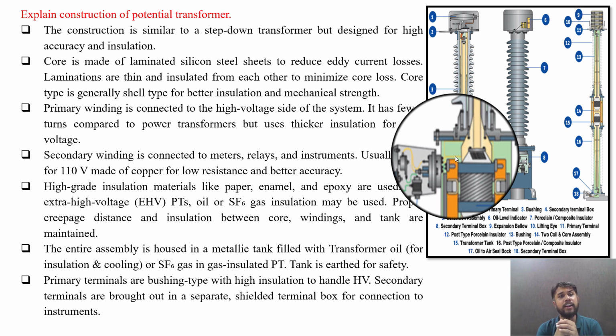This primary winding is connected to the high voltage side of the system, and it has fewer turns compared to the power transformer but uses thicker insulation for high voltage system. Secondary winding is connected to the meters, relays and instruments, usually rated for 110 volts, and the windings are made up of copper for low resistance and better accuracy.